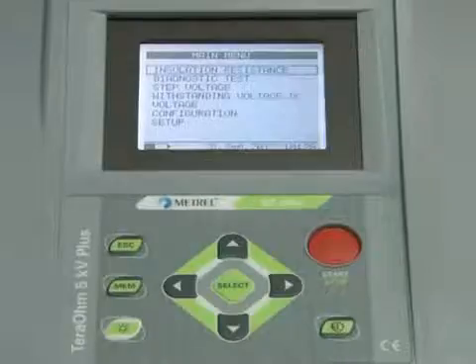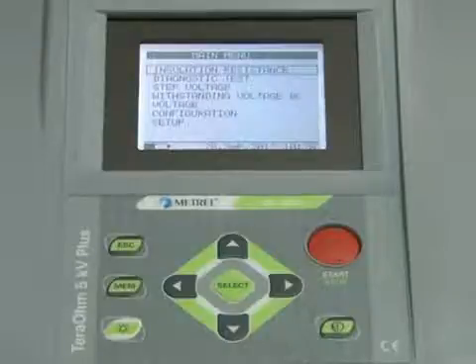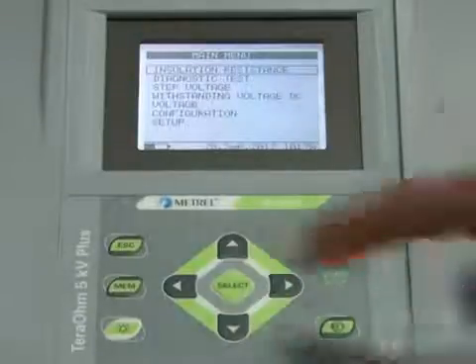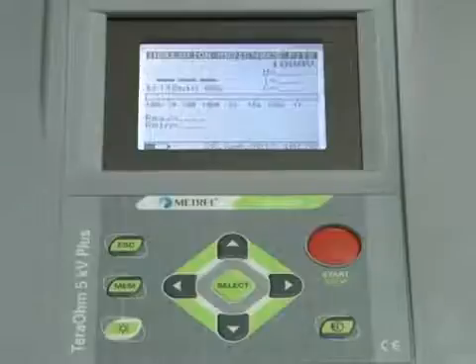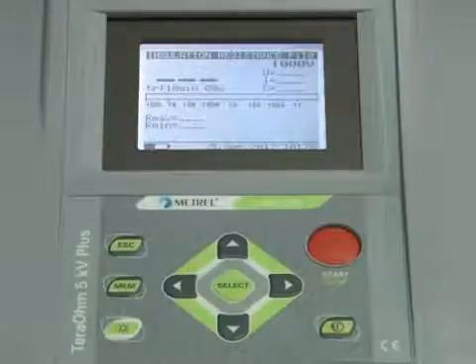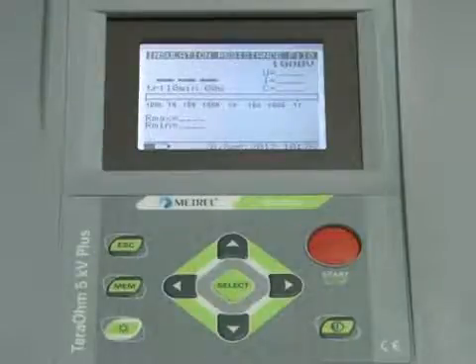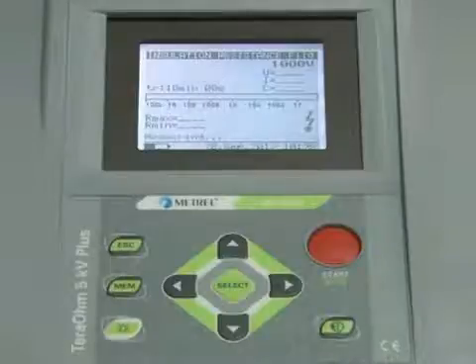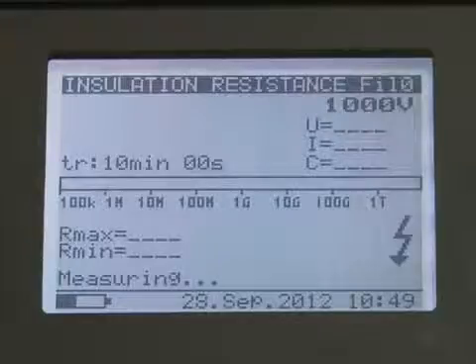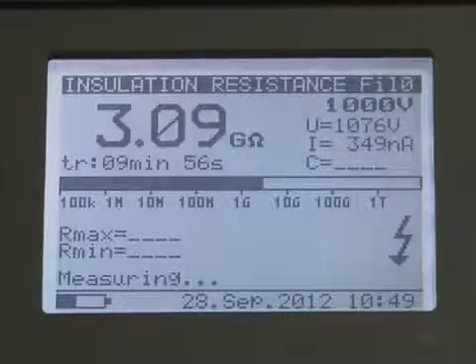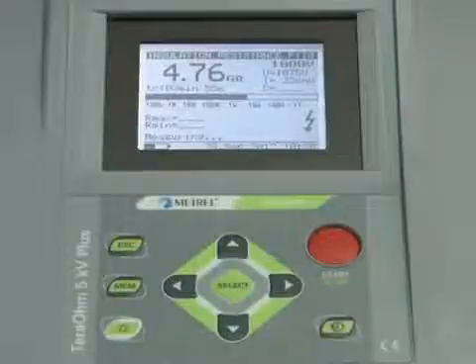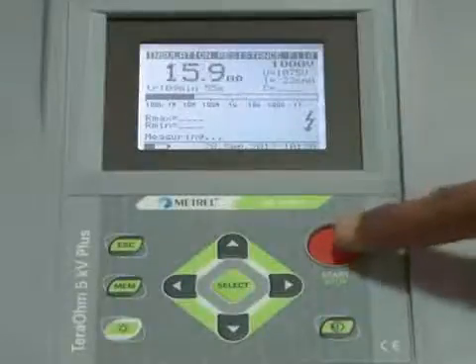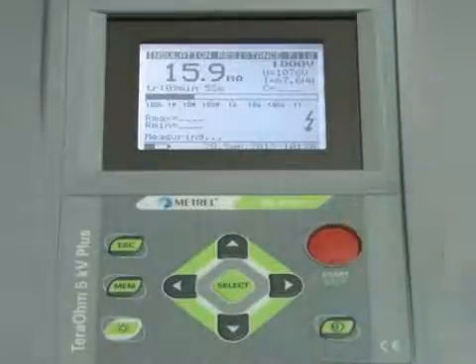For insulation resistance testing, the user connects test leads to the instrument and selects the insulation resistance function in the main menu. Pressing the start/stop key enables continuous measurement mode. Once the value stabilizes, the user can press the start/stop key again or wait for the timer to stop.